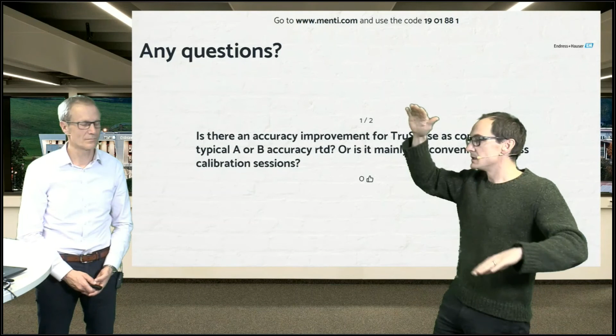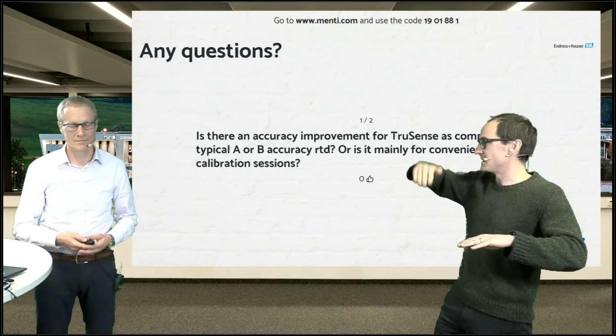The same thing happens in the TruSense. We have the PT100 and we have an electronic, so also the analog digital conversion, and you have to look at the complete thing. So again, to the question, the PT100 is the same. The accuracy of the sensor itself will not improve. What we look at in the complete system is the overall accuracy. With a TruSense, we do gain a better accuracy because we are matching that PT100 sensor to the electronic.